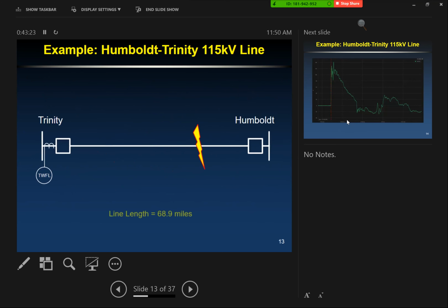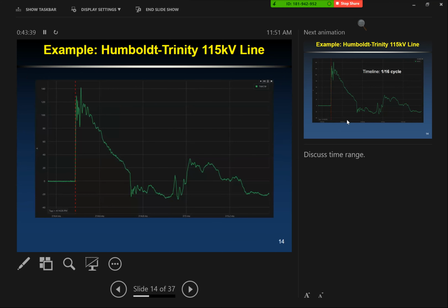And so here's an example of one of our lines that we installed this on. This is the Humboldt Trinity 115 kV line. You can see here it's about a 70-mile line, and so we installed the relay at the Trinity end. I'll step through an example of what the actual record looks like that you would find.